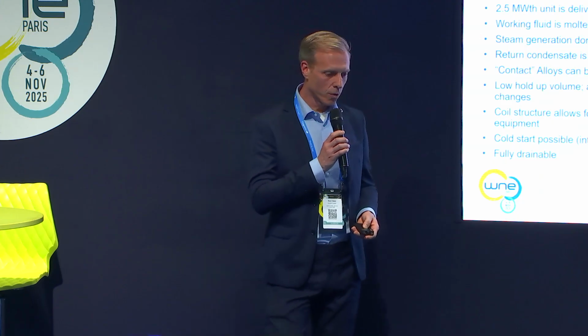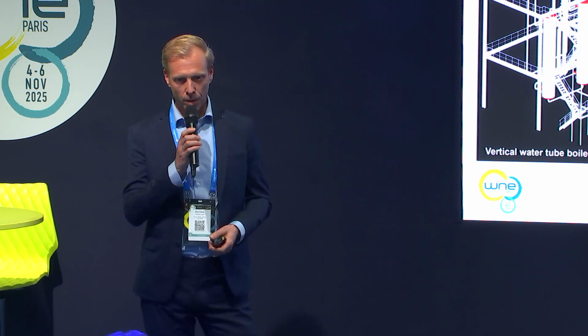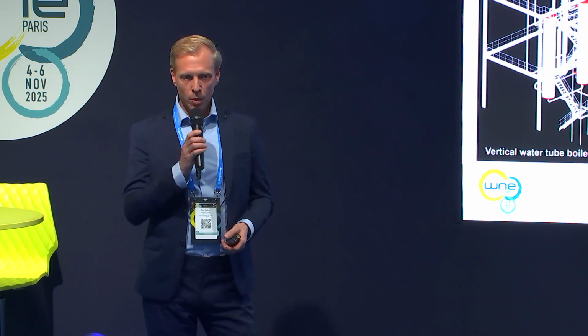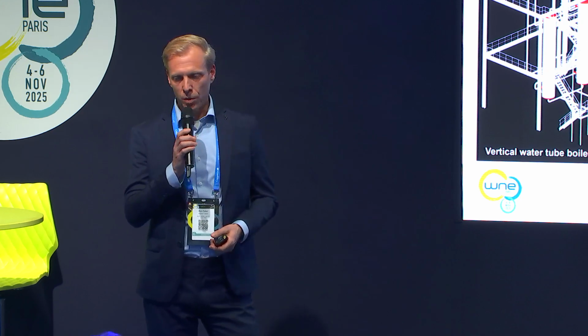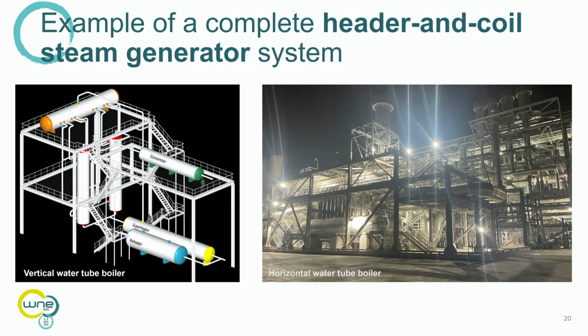So then we move to header and coil. Header and coil is a special type of shell and tube especially designed for molten salt use. Molten salts are particularly difficult to handle because they can be corrosive, and if you use traditional construction methods, the tube sheet could suffer from corrosion because there are crevices inside. In header and coil, we have solved this problem by carefully rerouting the tubes into the header, so there are no more crevices.